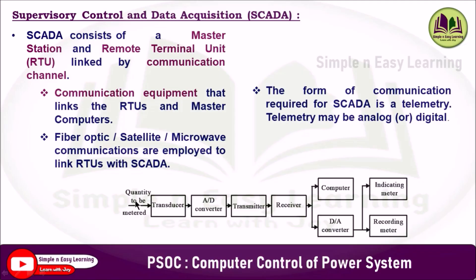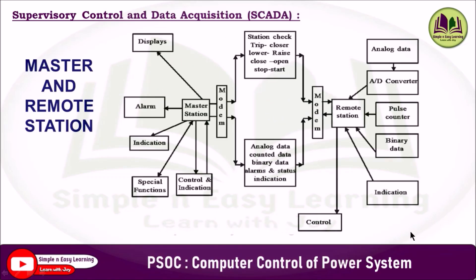The quantity to be metered is sensed with the help of sensors, and the physical quantity is converted into an electrical quantity using a transducer. That analog signal is converted to a digital signal and transmitted to the computer at the energy control center. There, the digital signal is converted back to analog and displayed on the indicating meter and sent to the recording meter.